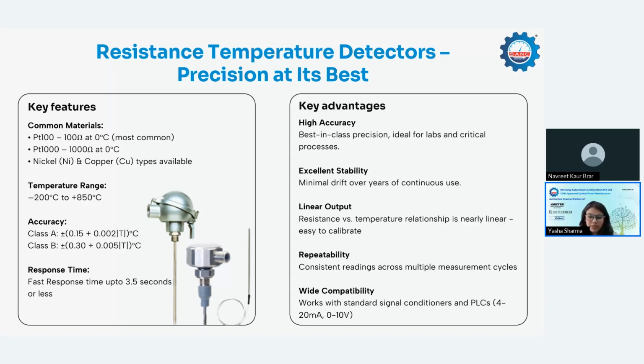Wide compatibility. Now you are taking the output and you have to give it to big systems like PLCs or SCADA. You need to measure that temperature, right? So RTDs are widely compatible with signal conditioners and PLCs. PLCs will have 4 to 20 milliamps and 0 to 10 volts according to your requirement.